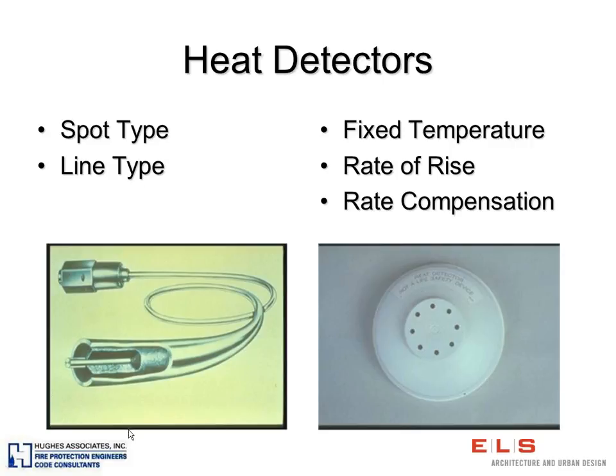And then a line type detector is this type of detector here. It's nothing more than a wire or a cable, and when it gets hot enough, it will impact this cable. You will have a tear or a melt, or something else will occur that it will essentially break the circuit on that line type heat detector.